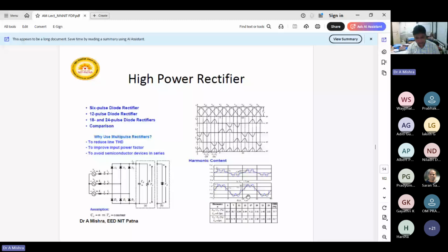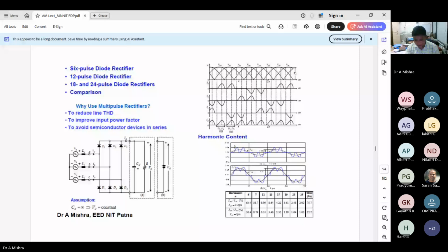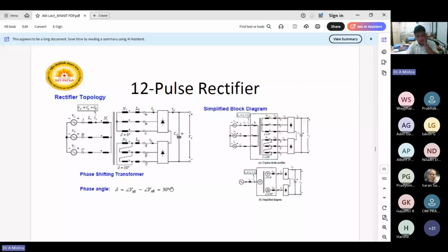THD level observed will be 32% in the current. If you are going for the 12 pulse converter, it is used with the star delta and star zigzag transformer. Phase shifting transformer will be used for making the two pulse converters operate at an angle difference of 30 degrees. So a 12 pulse converter is basically two 6 pulse converters connected in series with a phase difference of 30 degrees.